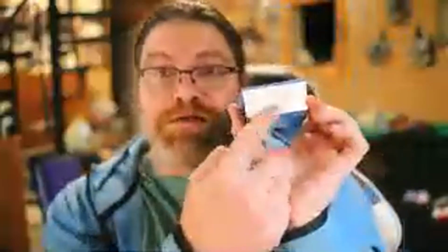And there's no room issue, because there's plenty of room on this packaging. It's a fairly large box. So it doesn't meet the requirements. I have plenty of space down here to put a UDI. It's not there. Maybe it's on the inside, but not on the outside like it's supposed to be. So as I promised you, we'd find a labeling issue already.